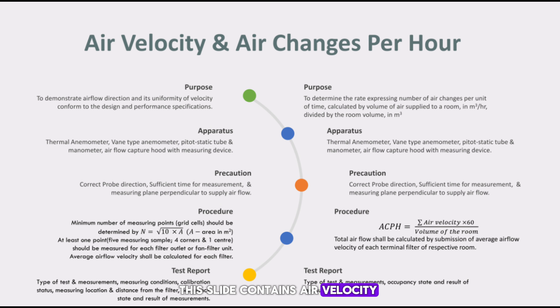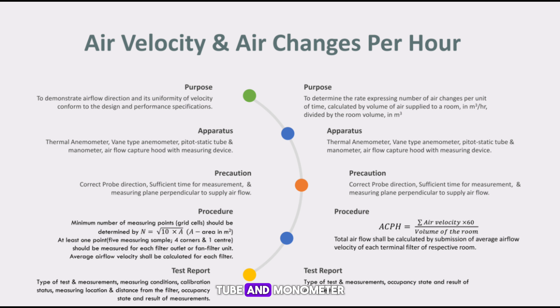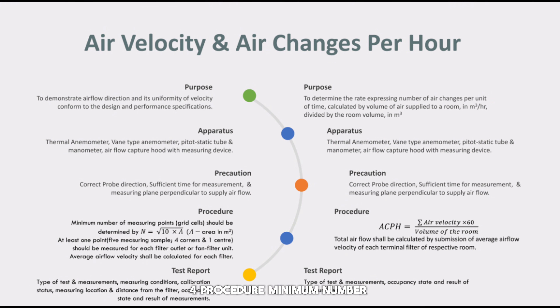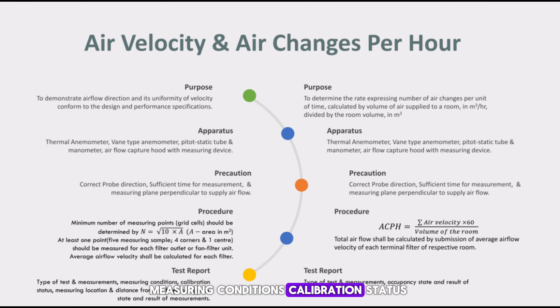Air Velocity Test — Purpose: to demonstrate airflow direction and uniformity of velocity conforming to design and performance specifications. Apparatus: thermal anemometer, vane-type anemometer, pitot-static tube and manometer, and airflow capture hood with measuring device. Precaution: correct probe direction, sufficient time for measurement, and measuring plane perpendicular to supply airflow. Procedure: minimum number of measuring points (grid cells) is determined by the formula N = √(10 × A), where A is area in square meters; at least 5 measuring samples — from corners and one from center — should be measured for each filter outlet or fan filter unit. Average airflow velocity shall be calculated for each filter. Test report includes: type of test or measurements, measuring conditions, calibration status, measuring location or distance from the filter, occupancy state, and result of measurements.